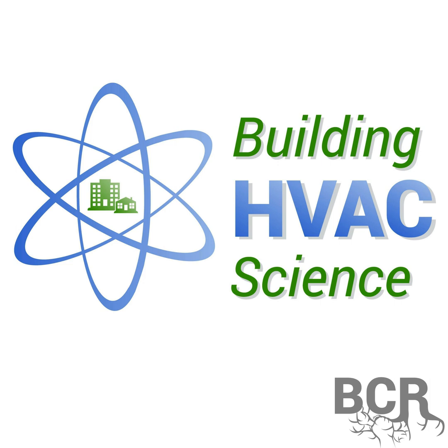And finally, at, say, minus 20 to minus 30 degrees Fahrenheit, it gets to where the temperature is low enough where the amount that you can compress up to a comfortable temperature has been reduced. And at that point, as is typical in any heat pump, you would have a coefficient of performance of 1, which basically means that the power that you put in the compressor is the heat that you're getting out, as opposed to a COP, or coefficient of performance, of 3, where you're getting, say, 2 units of heat from the outside coupled with a unit of energy from the compressor. So you're getting 3 units of total heat for every unit of electric energy put in the compressor.